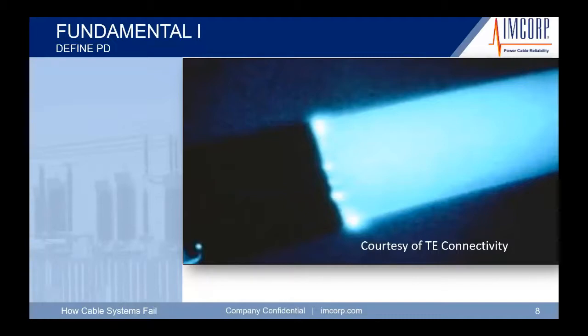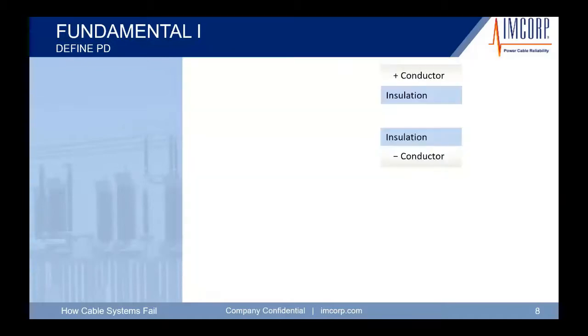Now, when the electric field is making its way through that cable, all of a sudden it's going to notice that its electrical field has been disrupted. When it sees that, it turns on itself very sharply. Now, this electrical activity, this glowing, which is known as corona, is a high level of electrical stress. That electrical stress is stronger than the dielectric strength of that insulation. So over time, not in one day, maybe not even in 3 months, this electrical stress will break down that insulation. So that cutback that you made of, let's just say 6 inches, is now creating a tracking path directly to the inner conductor, which will cause a fault.